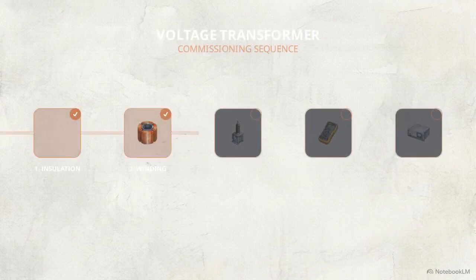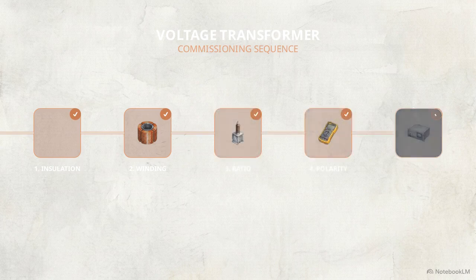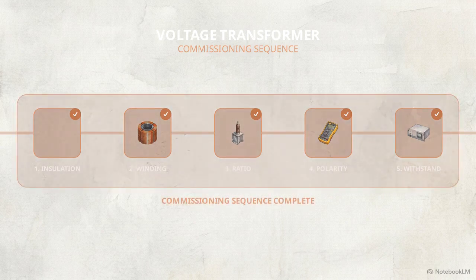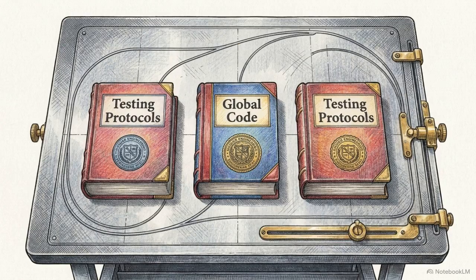This is a progressive series of diagnostic tests designed to systematically prove the physical boundaries and electromagnetic behavior of a voltage transformer, or VT, before it ever sees grid power. Every step of this process is dictated by overlapping global standards from organizations like the IEC, IEEE, and NEMA.